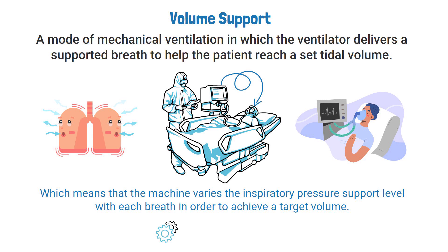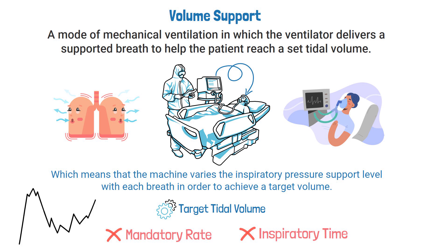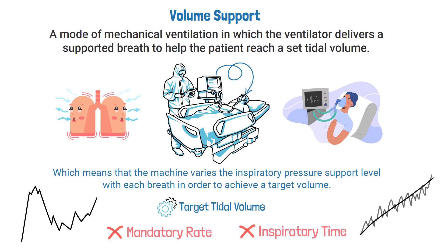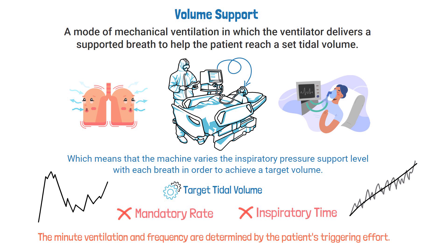In the volume support mode, the operator can set a target tidal volume but not a mandatory rate or inspiratory time. The machine then delivers breaths with variable pressure support levels in order to achieve the desired tidal volume. The minute ventilation and frequency are determined by the patient's triggering effort.